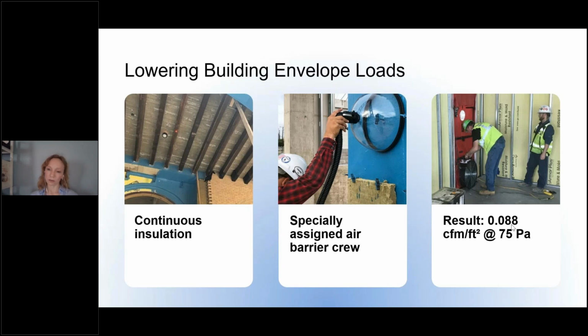an air tightness goal of less than 0.1 CFM per square foot at 75 pascals. Code is 0.4 for reference, at least in Texas, and Army Corps of Engineers is around 0.2 or 0.25. The owner wanted it tighter than that. When I say the owner, I mean the ownership, the credit union, and they incentivized it with a large bonus if this crew was able to hit the goal.